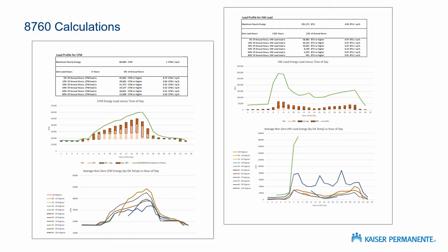8760 hours, right? If you've never seen an 8760 line calculation, they're pretty easy to come by. You can output it out of either Trace or your energy modeling software. It outputs all the variables for the design year, and you can pick which variables you want to output. So you can look at hot water GPM or air handler CFM, supply temperatures, whatever you want. And we want to look at these. We need to see your load profile. This spreadsheet that you're looking at here is a template that we have. We'll share that template with you. You're free to use it. But we want to see the narratives that are based on what comes out of these 8760-hour calculations. And it's a pretty radically different way of looking at design.